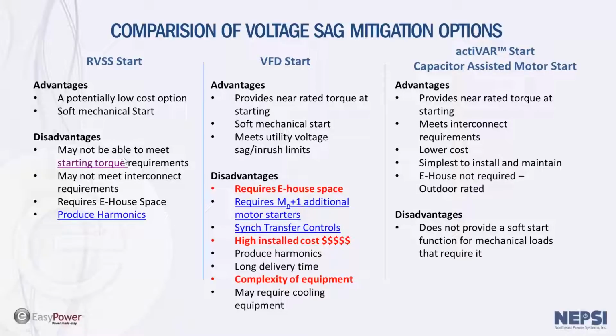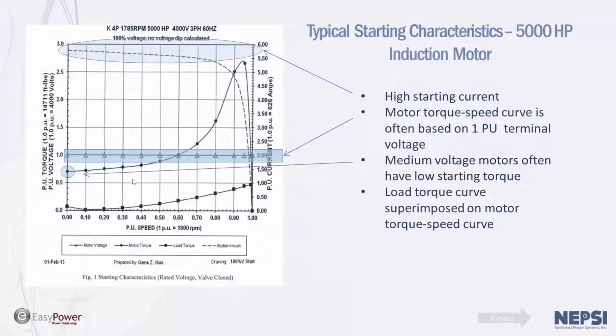One of the disadvantages, though, is that it may not meet the starting torque requirements for the application. One of the main reasons for that is that medium voltage motors in general have a low starting torque. For this typical speed torque curve for a medium voltage motor, you can see that the starting torque is around 0.7 at 1 per unit voltage, and this speed torque curve is drawn at 1 per unit voltage. So if the voltage is reduced to the motor, the starting torque will be that much less. The starting torque of the motor varies with the voltage squared, and therefore, for instance, if you have 1/2 the voltage to the motor, you're going to get 1/4 of the torque. For that reason, the motor may not want to start.